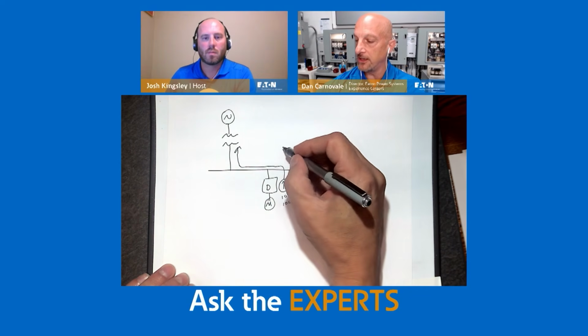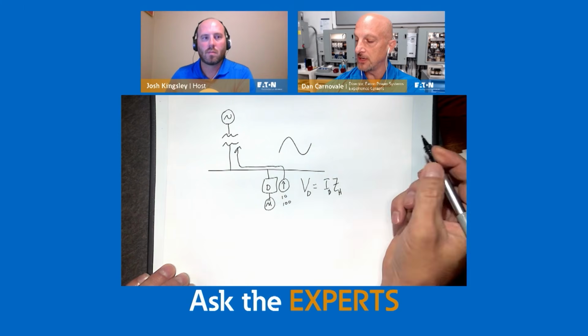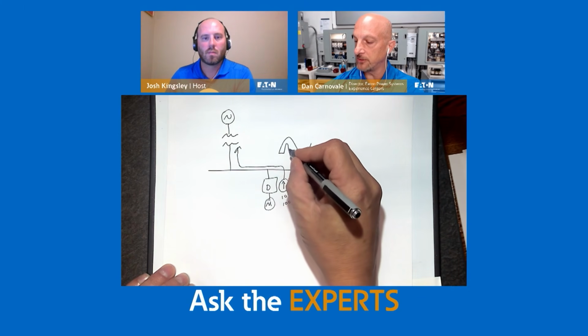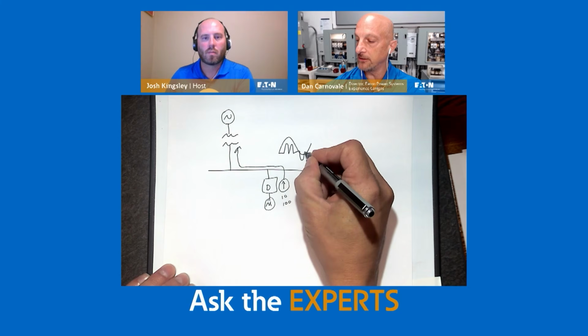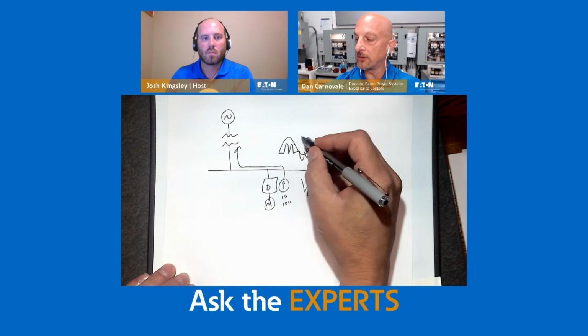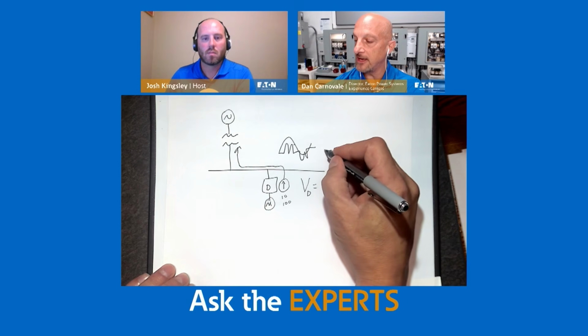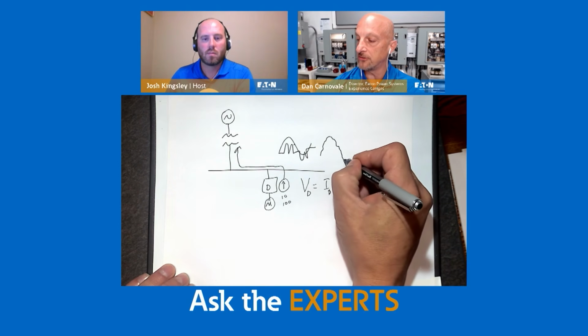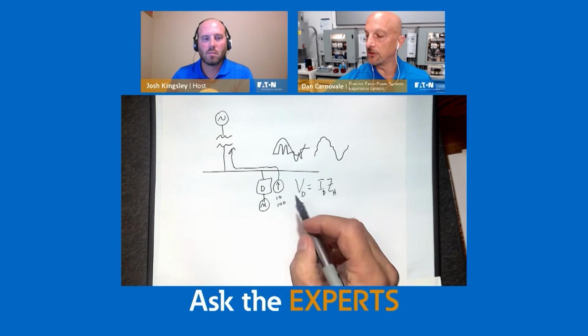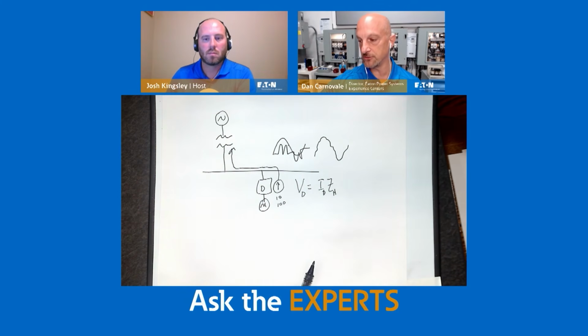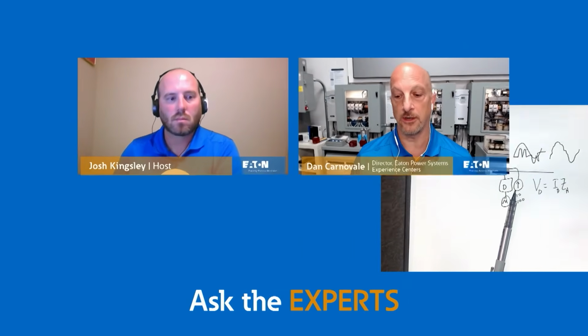So again, we start out with a relatively clean sine wave in terms of voltage. We draw a current that doesn't look like the voltage. We call that nonlinear load. And that nonlinear load, that current doesn't look like the voltage. That current pushing back up through the system then actually causes voltage distortion. So voltage distortion comes from current distortion. The more current distortion we have, the more voltage distortion we get. And again, great question to start with because harmonic currents come from the loads. Harmonic voltage distortion ends up being part of the end result of that. And so then the next step is how do you figure out what the solutions are, and how do you model the system if you need to determine what's the best solution for it.